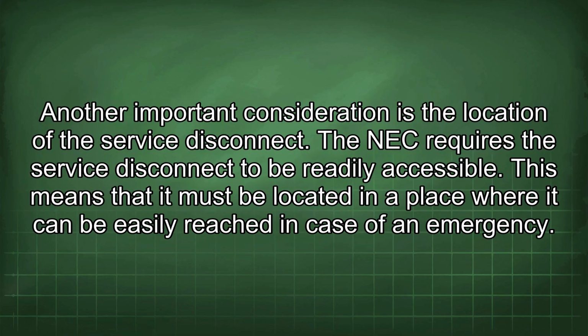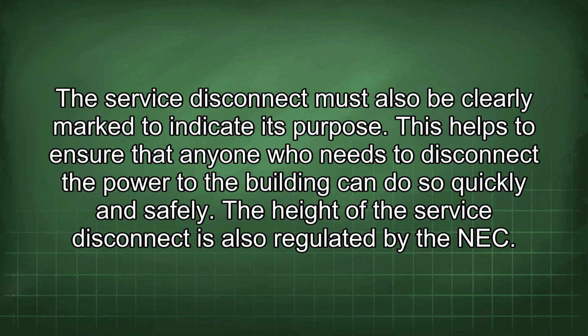Another important consideration is the location of the service disconnect. The NEC requires the service disconnect to be readily accessible. This means that it must be located in a place where it can be easily reached in case of an emergency. The service disconnect must also be clearly marked to indicate its purpose. This helps to ensure that anyone who needs to disconnect the power to the building can do so quickly and safely.